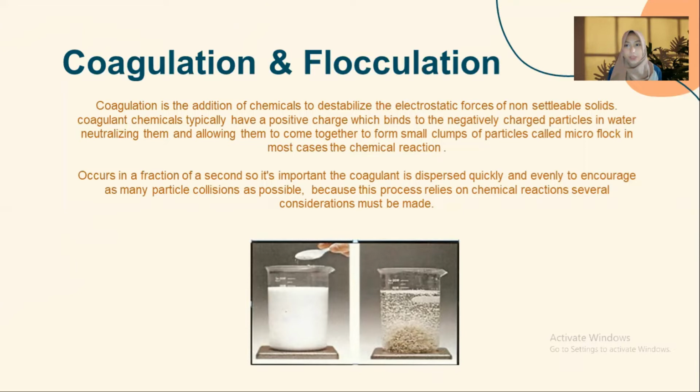Coagulation and flocculation. Coagulation is the addition of chemicals to destabilize the electrostatic forces of non-settleable solids. Coagulant chemicals typically have a positive charge which binds to the negatively charged particles in water, neutralizing them and allowing them to come together to form small clumps of particles called microfloc.